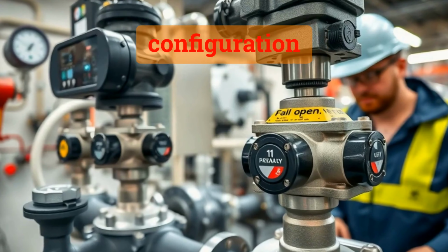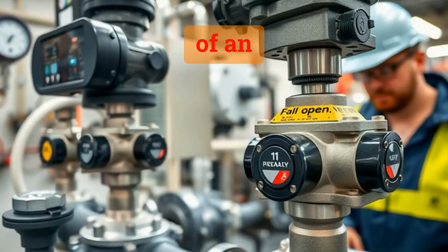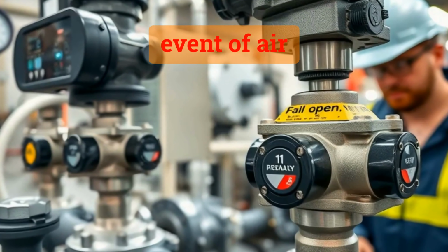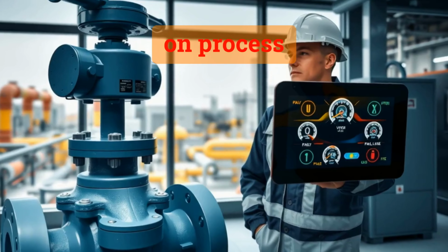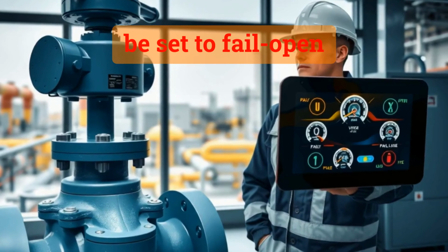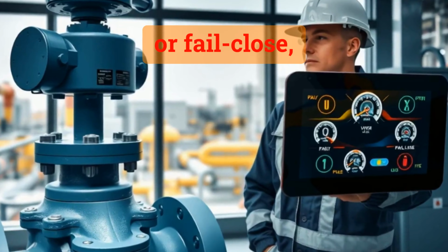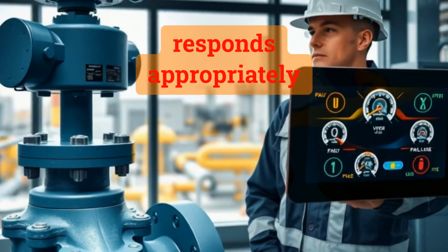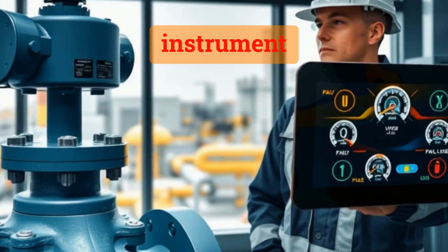Air-fail position configuration determines the default position of an air-operated valve in the event of air supply loss. Depending on process requirements, the valve can be set to fail open or fail close, ensuring that the system responds appropriately during power or instrument air outages.